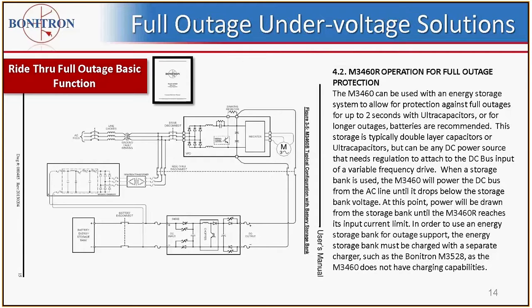And that's the basic function of the sag ride-throughs and the outage ride-throughs. And as I said, the only difference is where we're getting the energy to feed the voltage regulator booster, which feeds the drive. Now we're talking about full outage ride-through. And what happens is once the low bus threshold is reached, the ride-through turns on, and instead of pulling from the remaining AC line and boosting that 2-to-1 into the bus, we pull from a battery bank. So once again, there's no efficiency losses with double conversion or anything like that.